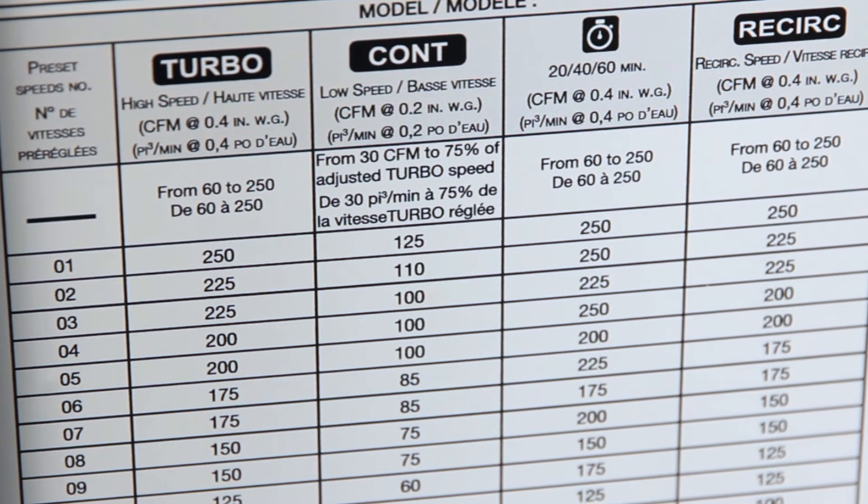You may choose between two easy balancing options. Preset speeds, where you will only need to balance the unit on turbo speed. Many preset speed ranges are available on these unit models. Use these speed ranges for balancing the unit using a specific CFM, which you'll find on the inside panel door of the unit.